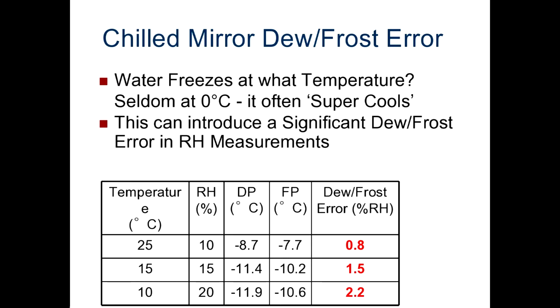Well, the problem is you may not know if it's dew or frost. And if you don't know, we can see this dew-frost error can be quite significant. At 25 C and 10%, as we can see in the table, you can have an error or an uncertainty just from the dew-frost of 0.8% RH. And that goes up to 2.2% when it's at 10 degrees C and 20% RH. So although we have very accurate capabilities, unless we know the dew or frost state on the mirror, the introduced errors can be quite significant. So this is something one must take into account when using a chilled mirror hygrometer.